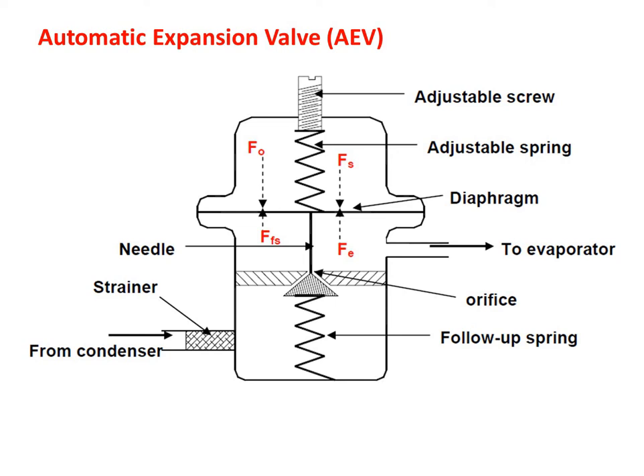An important characteristic of the AEV is that it closes off tightly when the compressor cycles off and remains closed until the compressor cycles on again. It has relatively poor efficiency compared to other refrigerant flow controls, as it permits only a small portion of the evaporator to be filled with liquid during heavy load periods. The constant pressure characteristic limits the capacity and efficiency of the refrigeration system at times when high capacity and efficiency are desired. If the load on the evaporator falls below a certain level, the valve may overfeed the evaporator, causing liquid to enter the suction line and potentially damage the compressor.